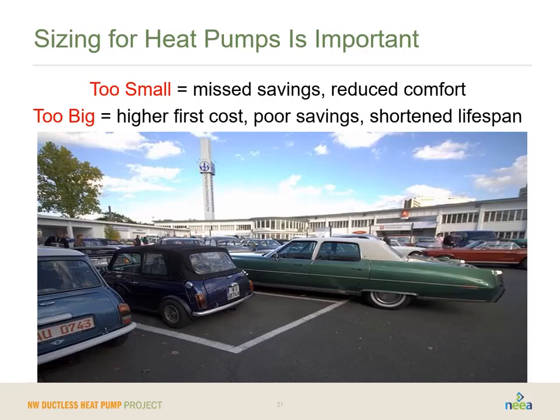On the other hand, if you make them too large, you are increasing the first cost, because up front the manufacturers and distributors will charge a little bit more for a larger system. So if you radically oversize in your design, you're actually increasing that first cost and maybe even losing out on some sales. You also may not get the savings you think you're going to get. Or the homeowner, in this case, wouldn't really get the savings they think they're going to get.